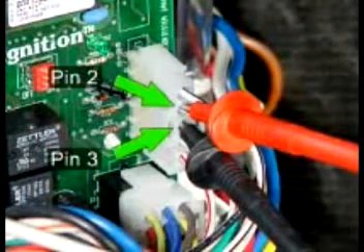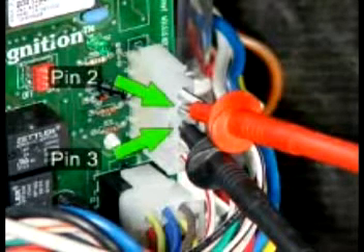If voltage is present, the IFC board green LED labeled RPM should be flashing slow. If it is not, check for 13 volts DC on the IFC board. Measure at the 5-pin plug between pins 2 and 3. If voltage is not present, replace the IFC board.